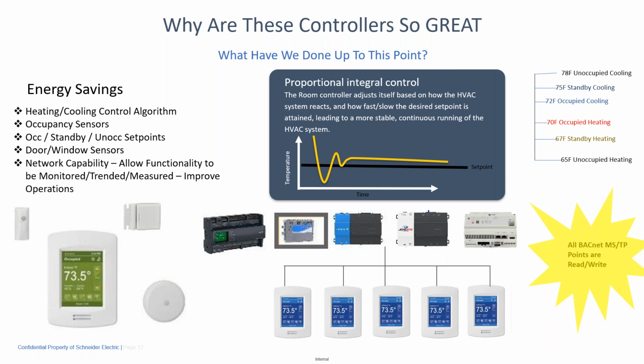When there's motion in the room, I control to occupied set points. If I don't sense motion, it starts a timer, right? After a half an hour, let's say, you can go to the standby set points. In this example here, I go from my 70 and 72 to 75 and 67. So maybe there's a conference room or something like that where I don't want to go all the way to unoccupied set points.